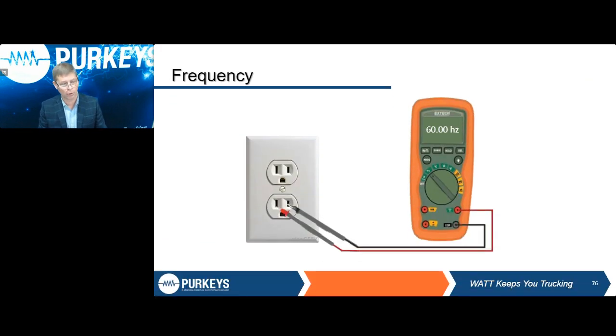Frequency. More and more trucks we have inverters. One of the things we can check on an inverter is the hertz of the AC outlet. Everything in the US is 60 hertz. You may have a driver complaining that devices aren't working properly or whatever. You can use your frequency function to check the hertz of the output of an inverter.